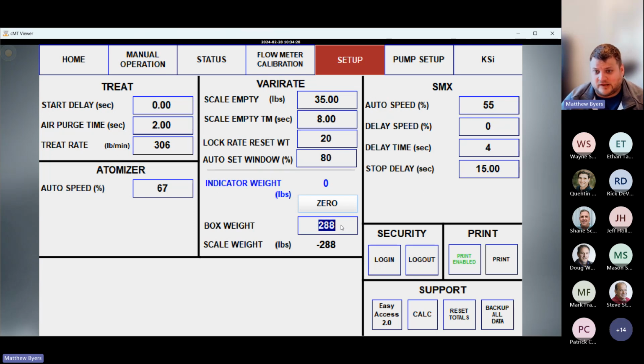That lid's about 20 to 25 pounds, depending on the box. Most boxes are around that 290 to 300 pound mark without a lid, 320-ish with a lid. But basically, as long as you type in a weight here for your empty box, if you come in one day and you notice your scales climbed a little bit or walked a little bit, they do that a little bit as the load cells heat up throughout the day.